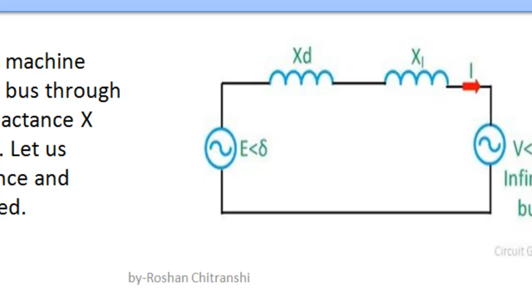Now note that the only way to vary load angle is by varying the input of the turbine. This is very important. If we change the input of the turbine, then we can vary the load angle or the torque angle as well as the power angle. The input of the turbine can be maintained or changed with the help of the prime mover. In the alternator, sometimes we prefer to change it with the help of an excitation system also, right?